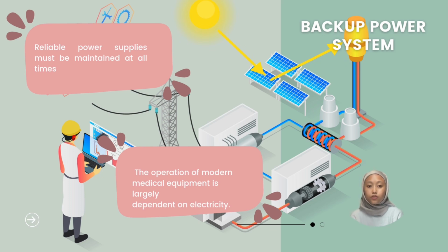These systems are referred to as a layer of security. Modern medical devices rely heavily on electricity to function. Ventilators, dialysis machines, and anesthesia equipment require a constant source of power to operate. A backup power system needs to have a large capacity to generate energy and be able to step in quickly to take over the power supplies and ensure that this vital equipment continues to function even when power outages occur.